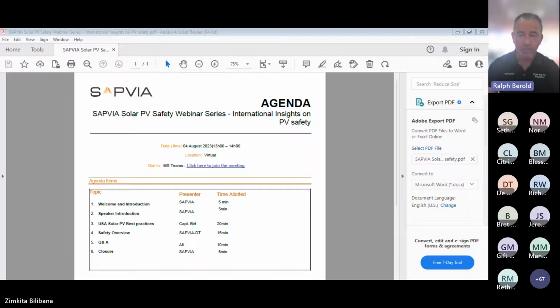It's a 95 to 97% install rate with a battery. So let's talk a little bit about that connection of high voltage DC, arc fault, no rapid shutdown next to a battery. We looked at battery chemistry, millions of dollars of tests, 20 years of testing. I've consulted for Tesla, Sunrun, I consult for Enphase. What we're looking at here is battery chemistry, NMC chemistry. The Tesla Powerwall is a good example. NMC chemistry has fire activity.